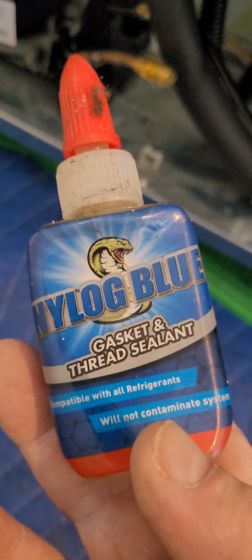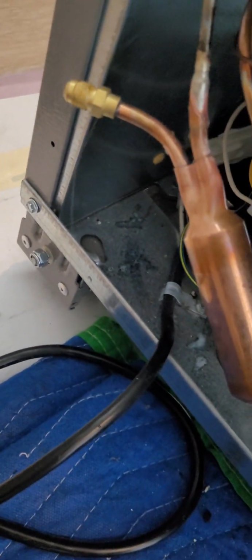Okay, pressures and temperatures, everything looks good, so we're going to cap this unit off. I'll use a little bit of Nylog Blue from Refrigeration Technologies, just a little dab will do ya. A little bit on the high side, just enough to seal off those threads and be preventative more than anything. The caps do have a rubber gasket inside, but let's just go the extra mile.